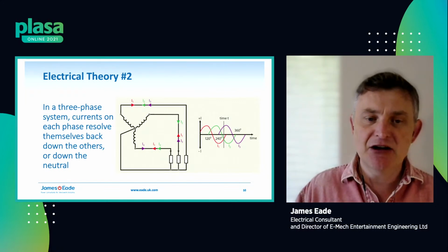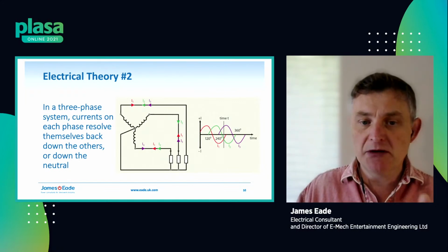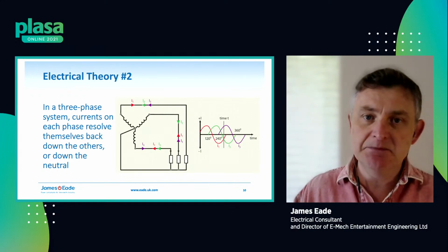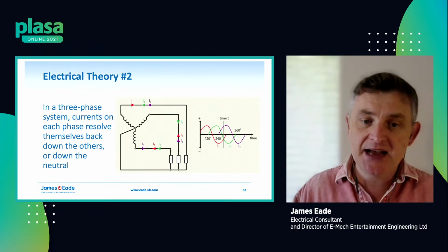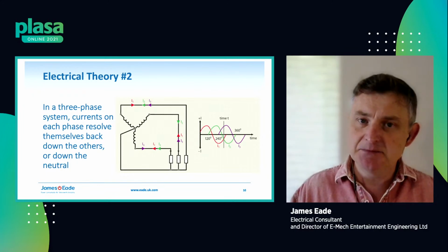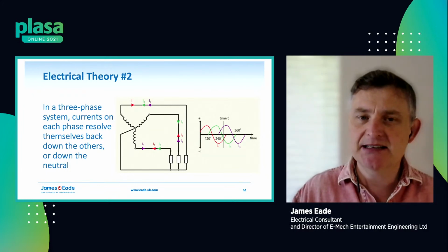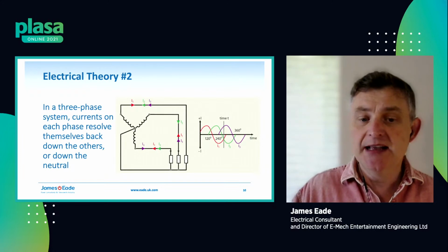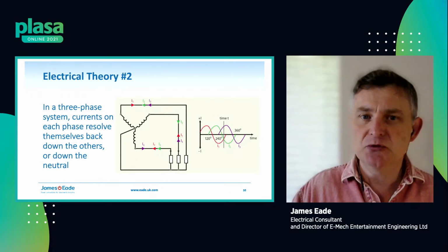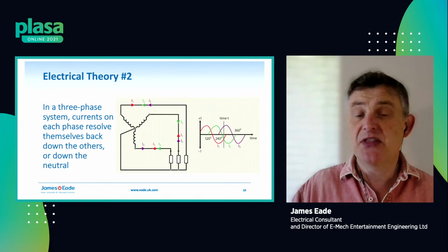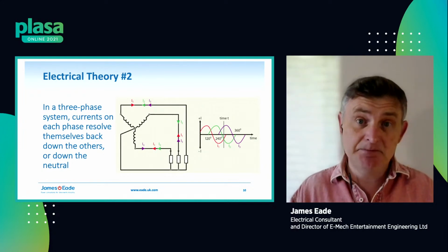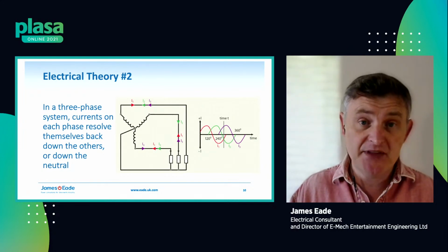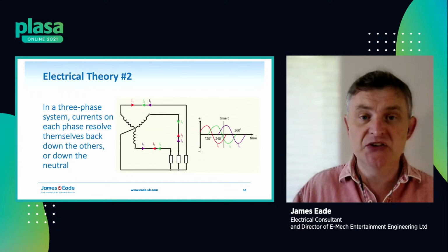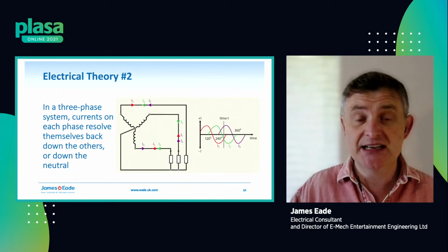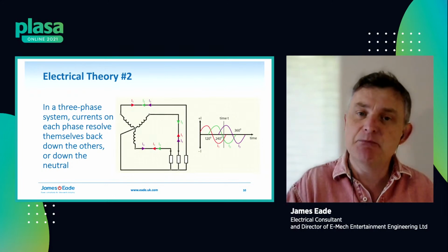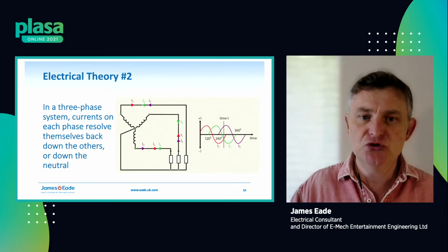If you imagine current coming out of phase 1, you've got I1 flowing out of the winding, down through the load, and in a balanced system, that current actually flows back down loads 2 and 3. So no current goes down the neutral in a balanced 3-phase system. That's why motors, chain hoists, and similar only have a 4-pole connector - you have the 3 phases and the protective conductor or earth, because it's a balanced load. It doesn't need a neutral.